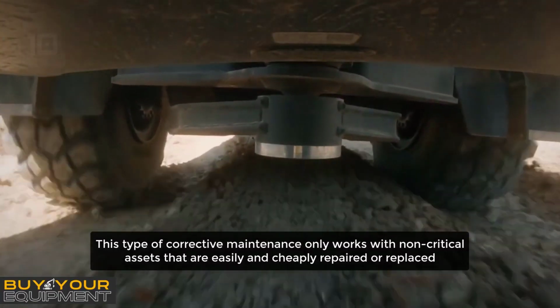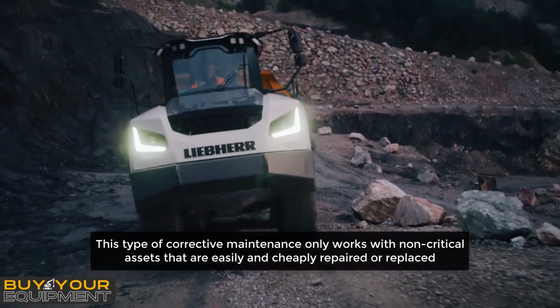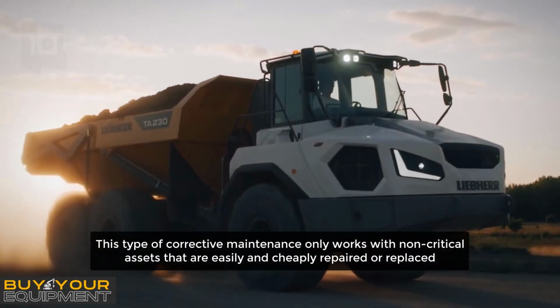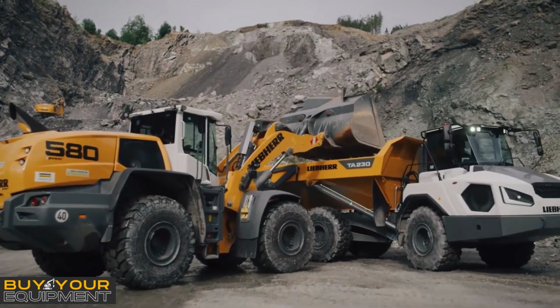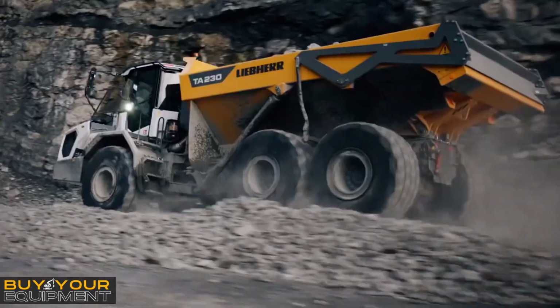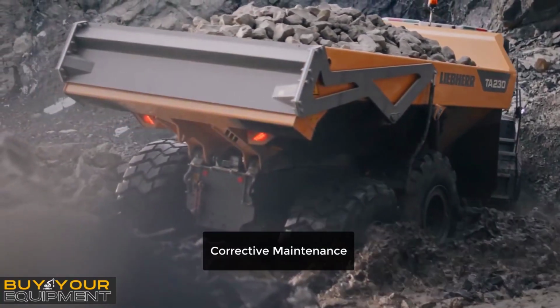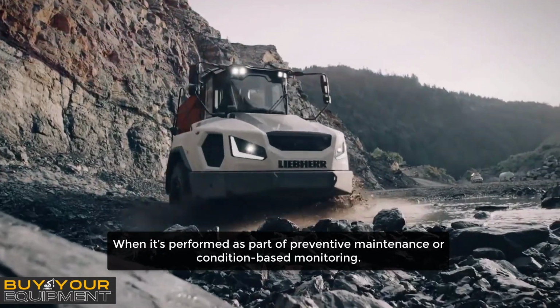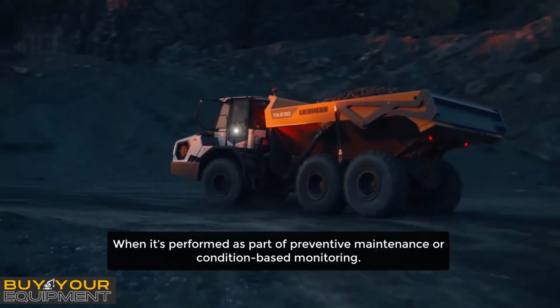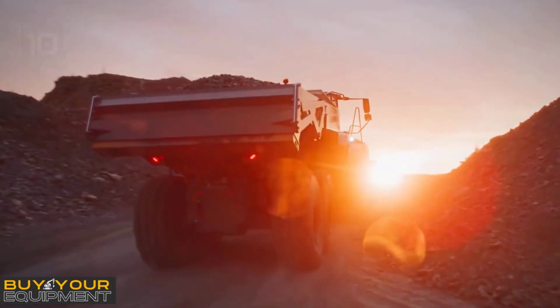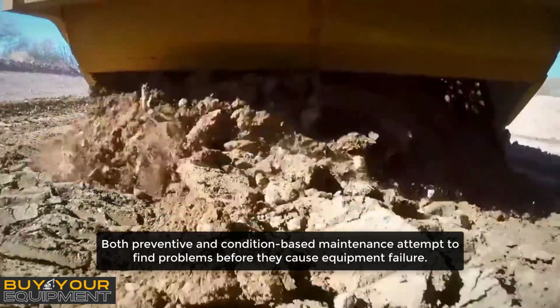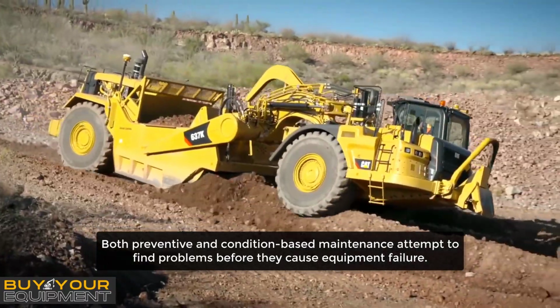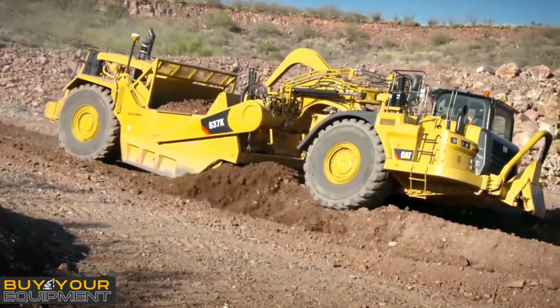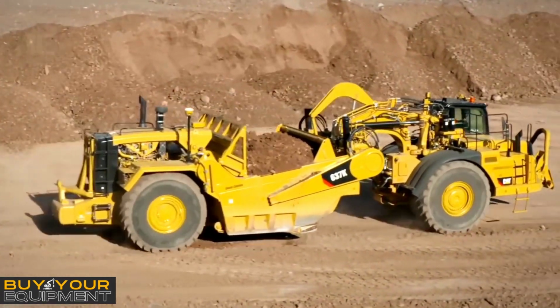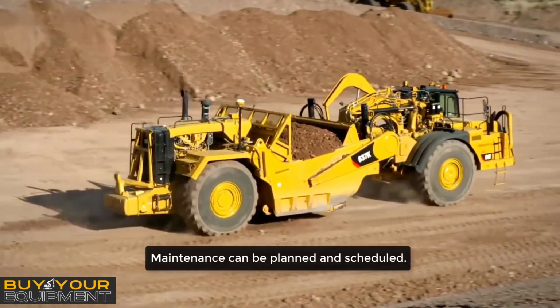This type of corrective maintenance only works with non-critical assets that are easily and cheaply repaired or replaced, or with systems that have redundancies. Number 2, corrective maintenance is planned when it's performed as part of preventive maintenance or condition-based monitoring. Both preventive and condition-based maintenance attempt to find problems before they cause equipment failure. If a problem is found, maintenance can be planned and scheduled.